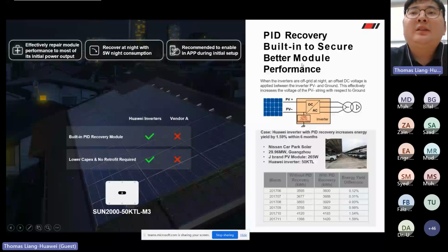So as I mentioned earlier, this inverter can support the PID recovery function, which has the PID module built in the inverter. PID is short for potential induced degradation, and it normally happens in high temperature, high humidity scenarios. The PV module's capacity can be affected by the temperature and humidity, so you cannot use the full capacity of the PV module, and the efficiency will also be affected.